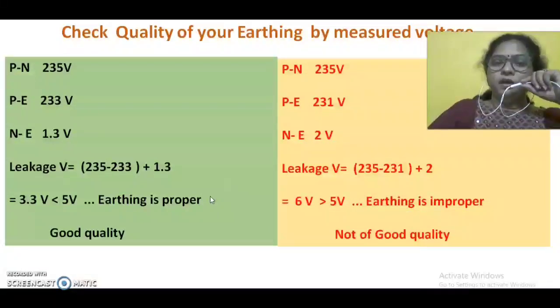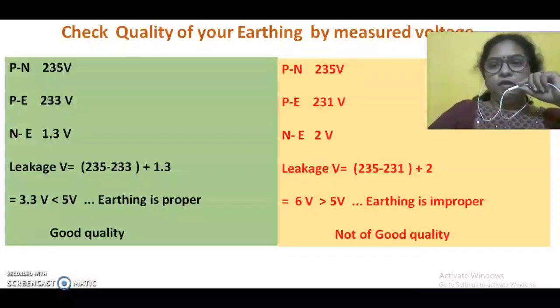But in the other case, if your phase and neutral voltage is 235 and phase and earth is 231, then this difference is 4 volt, and if neutral to earth, for example, is 2 volt, then 4 plus 2 is 6 volt. So if this leakage voltage is more than 5 volt, then your earthing is not proper, so your earthing is not of good quality. In this way, by measuring voltage, you can check the quality of earthing, and you will come to know whether your earthing is there or not at your house.